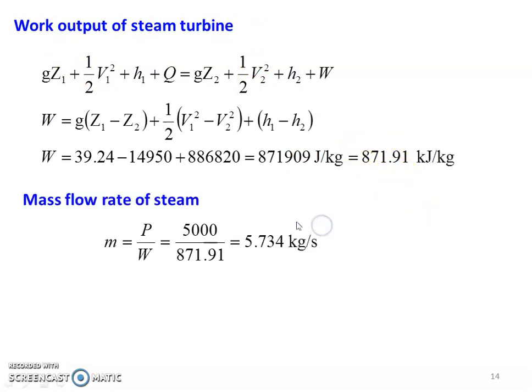Mass flow rate of the steam: M equals power divided by work done. Power is 5 megawatt equals 5000 kilojoules per second. So M equals 5000 divided by 871.91, equal to 5.734 kilograms per second. That is the amount of steam flowing through the turbine.